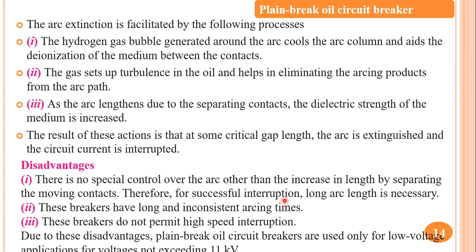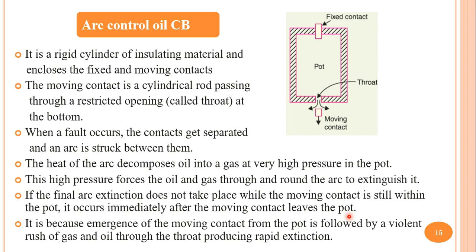Plain break oil circuit breakers do not permit high-speed interruption. Because of these disadvantages, they are used only for applications below 11 kV. Instead of plain break oil circuit breakers, arc control oil circuit breakers are used for higher performance requirements.